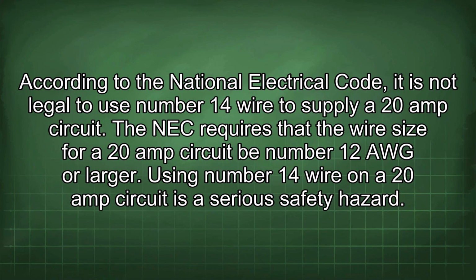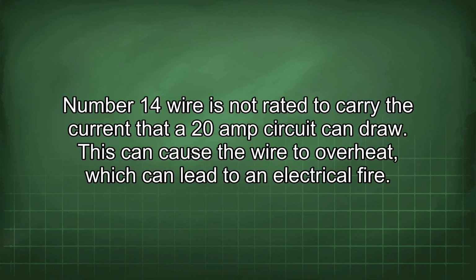According to the National Electrical Code, it is not legal to use number 14 wire to supply a 20 amp circuit. The NEC requires that the wire size for a 20 amp circuit be number 12 AWG or larger. Using number 14 wire on a 20 amp circuit is a serious safety hazard. Number 14 wire is not rated to carry the current that a 20 amp circuit can draw. This can cause the wire to overheat, which can lead to an electrical fire.